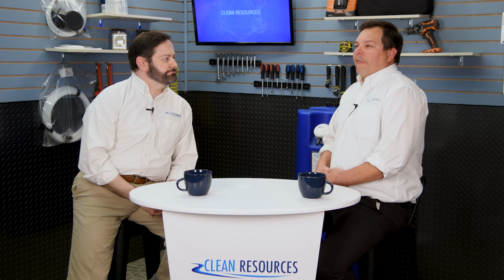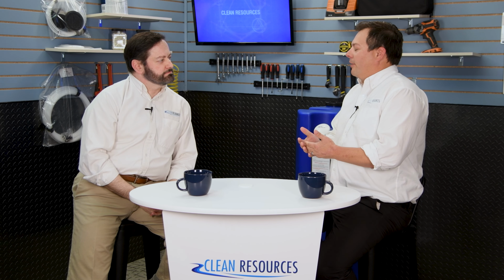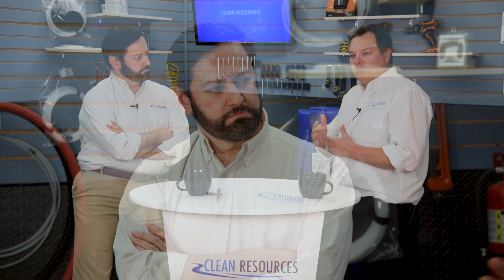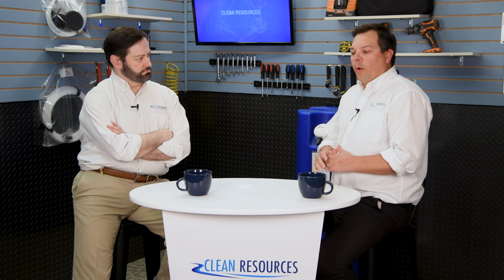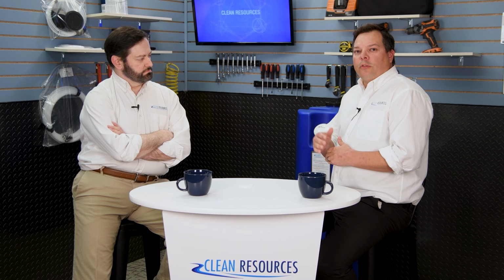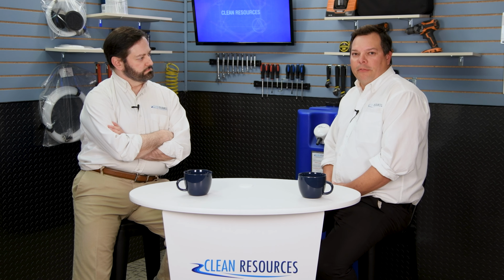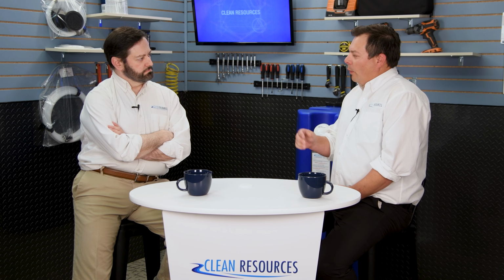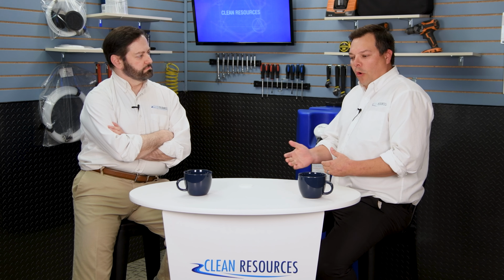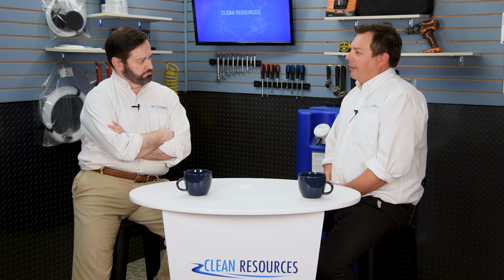That's great. So what do you see as the most common issues for overflowing through the vent? Most typically what we see, if I was going to diagnose it or summarize it into one word, it would be an obstruction. What most end users, installers, service techs do not see is the functionality of the system. When compressed air pushes the condensate into our unit, we decompress all of that pressure, which relies now solely on gravity flow to discharge the condensate. So any obstruction in the unit will cause the unit to eventually overflow out the vent.